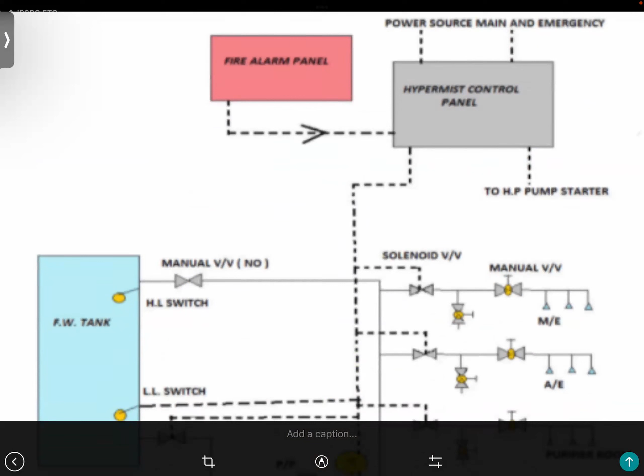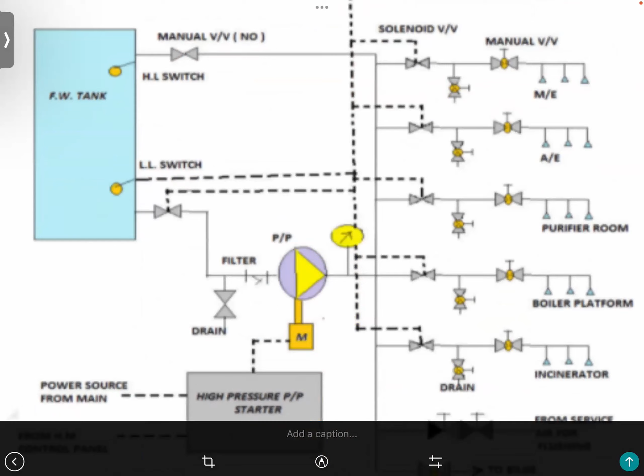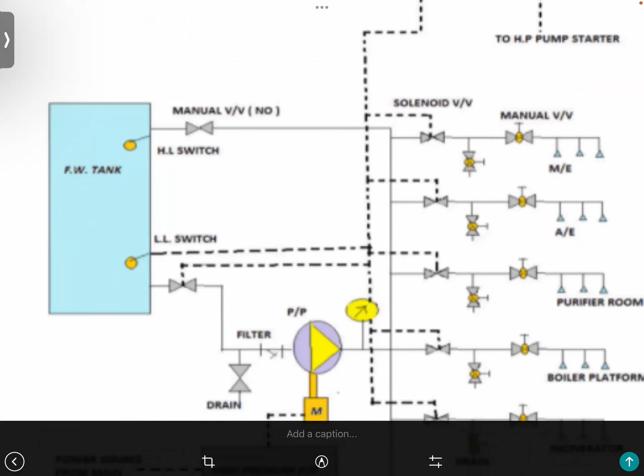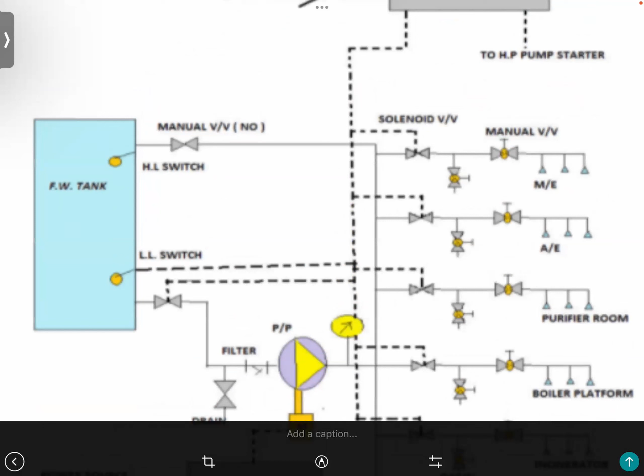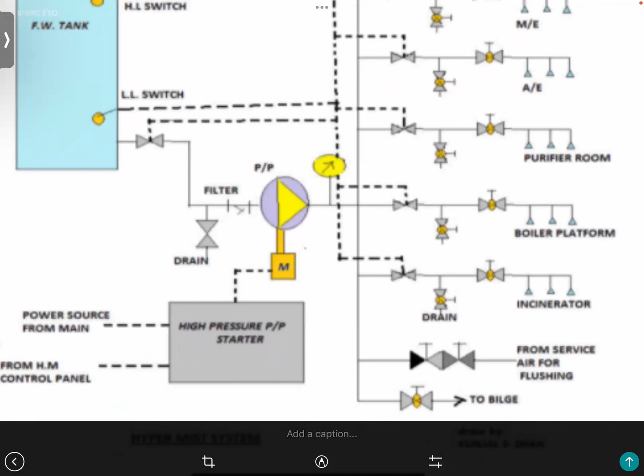So what is happening basically? The activation generally takes place by two different types of detectors. Suppose on the main engine there are two different types of detectors. When both of these activate, it will give a signal to the pump to start, and the signal goes to the starter. It will give the signal to the hypermist control panel. The fire alarm panel is also giving feed to the hypermist control panel. As the detectors get activated, the control panel will give a signal to the pump, and it will also give a signal to the solenoid valve.